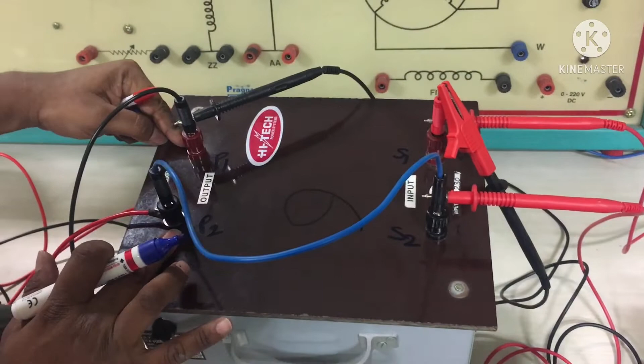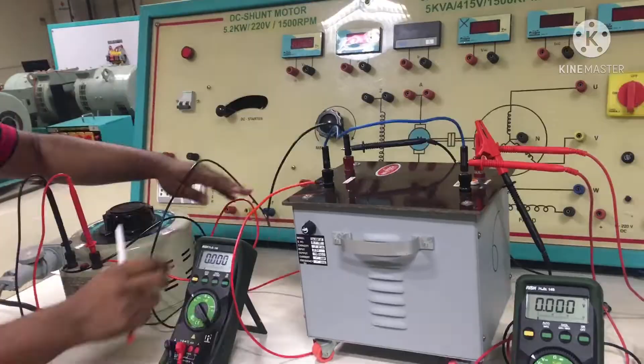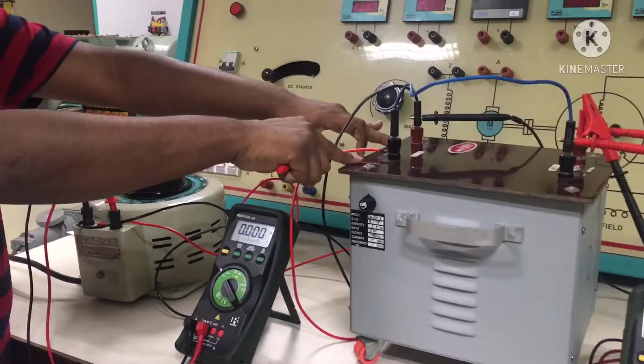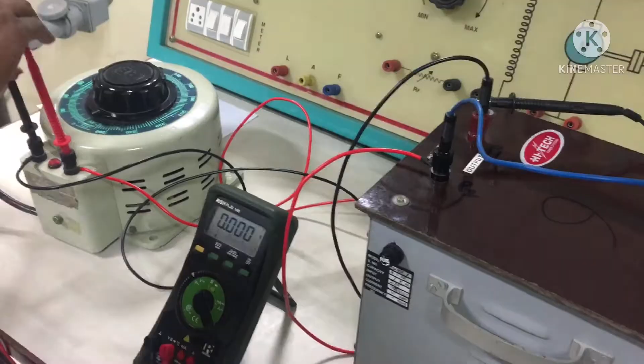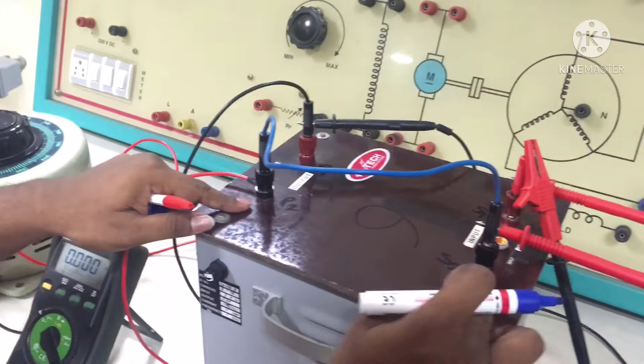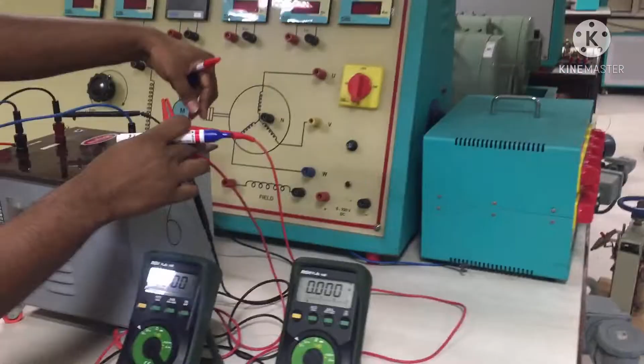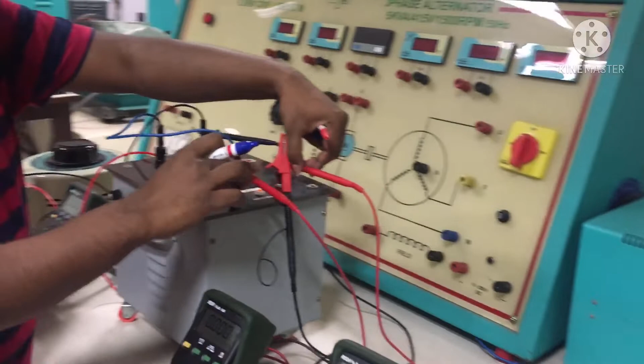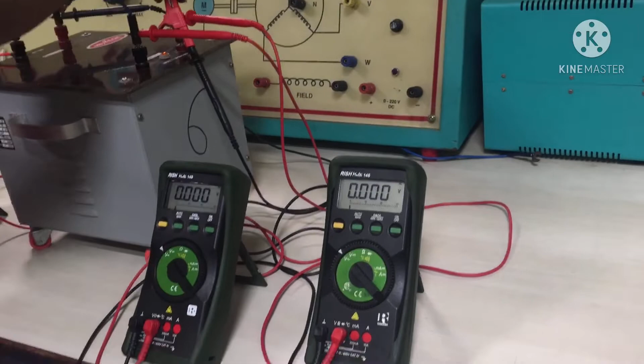In between these two we have the primary winding, in between these two terminals we have the secondary winding, and the primary winding is connected across the auto transformer output. We have connected one voltmeter across this primary winding of the transformer, or we can connect it across the output of the auto transformer, because the output and transformer primary are both connected in parallel. P2 and S2 we have shorted here, and in between S1 and S2 we have connected voltmeter 2, and in between P1 and S1 we have connected voltmeter 3.